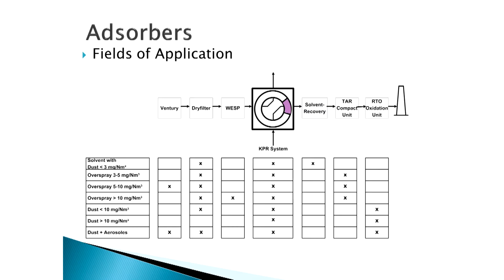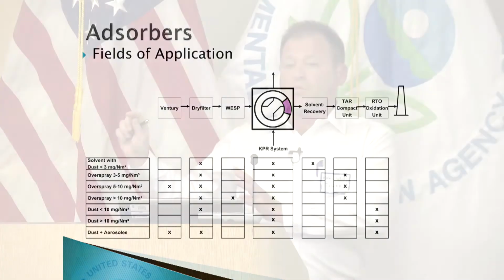The media is very, very sensitive to dust. So in most concentrator systems that you see, there could be upstream prefiltration ahead of the device. And that's something we have to examine very closely. Even in a process where the process may have its own filtration, we have to be very, very careful about what's coming to us, because the media is expensive, and the last thing we want to do is plug it up with particulate.